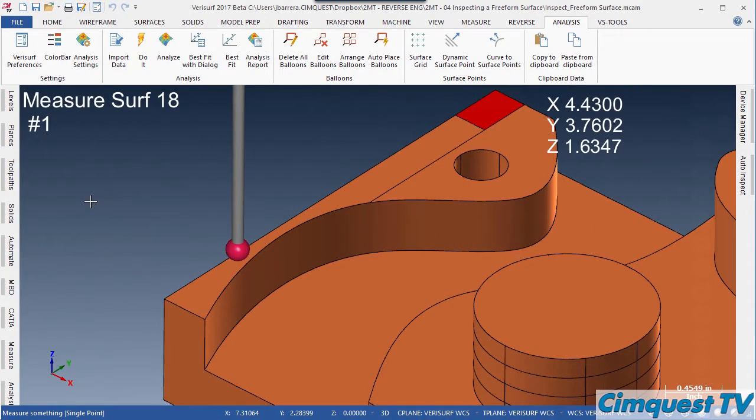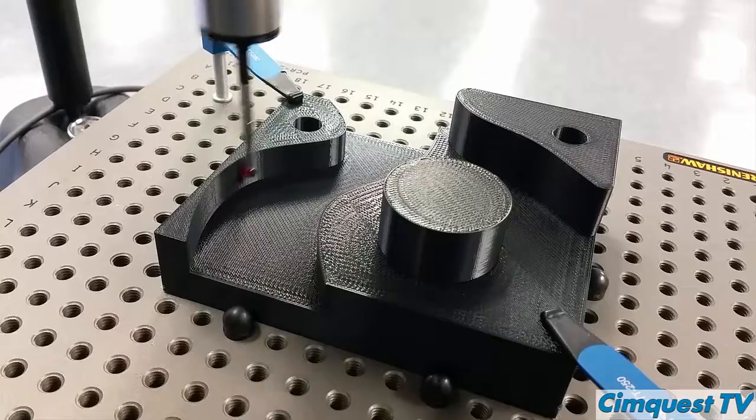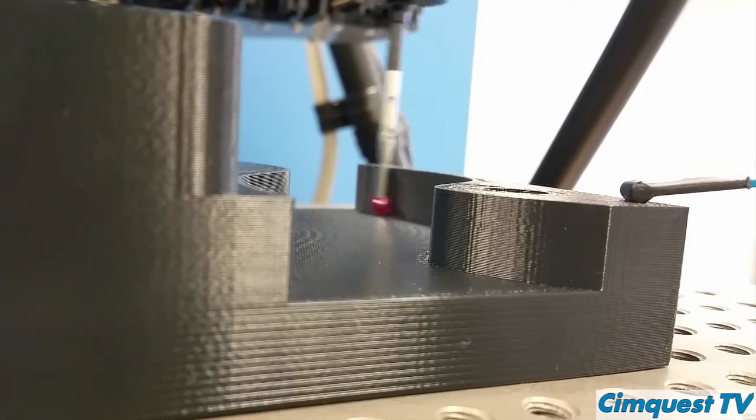Once I finish programming the probe path, I use the CMM master to inspect it. The probe then follows the automated repeatable path created in the Verisurf software and quickly scans and collects the data from each grid point.